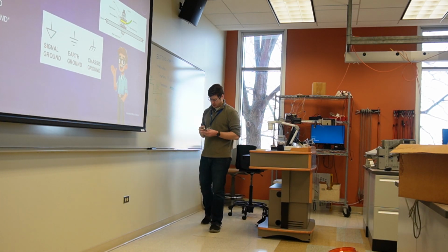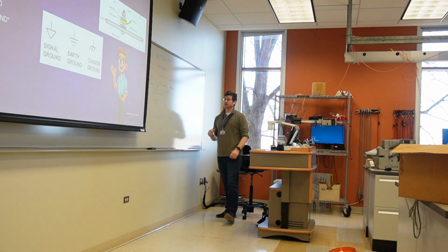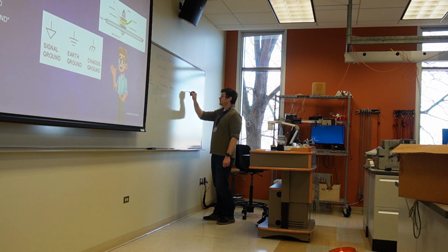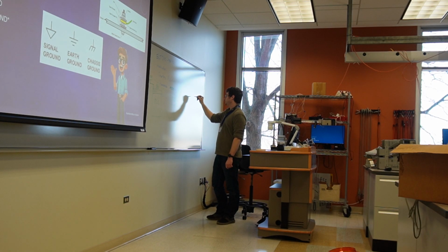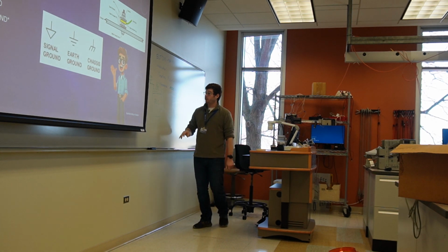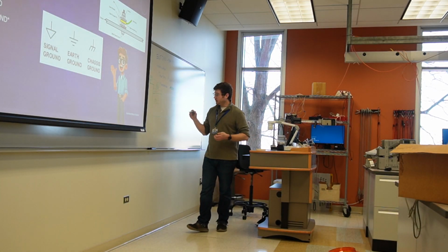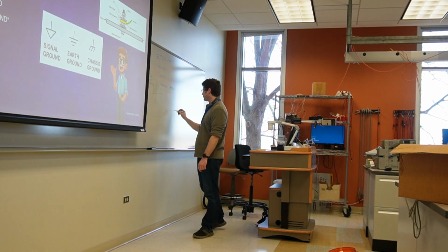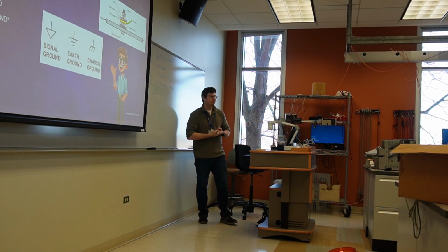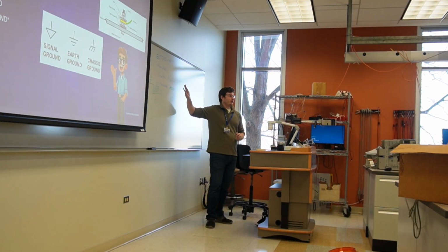One thing always good to keep in mind, especially for our PLCs or any systems that are talking to each other galvanically, means metal contacting metal. Galvanic contact. If we have a PLC talking to a power supply that also may have a sensor, you must have all of those grounds connected. All of these have to have a ground and they all should be common to each other, touching each other through some means of wire. Small tangent there, but I just wanted to get that out of the way so you know what I'm talking about when I start to draw stuff on the board.